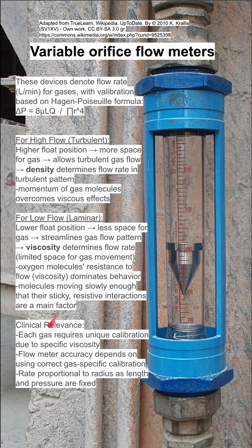For clinical relevance: each gas has a unique calibration due to its specific viscosity, and flow meter accuracy depends on using the correct gas-specific calibration. You will need to change the markings that denote flow rate for each gas. The rate of flow is proportional to radius, as length and pressure are fixed for a certain flow rate.